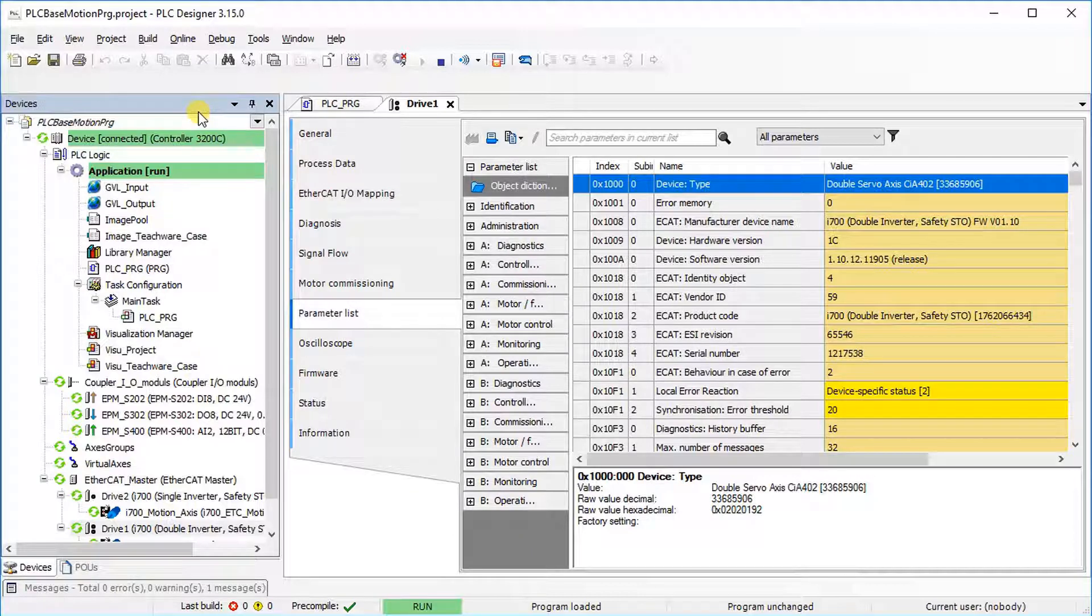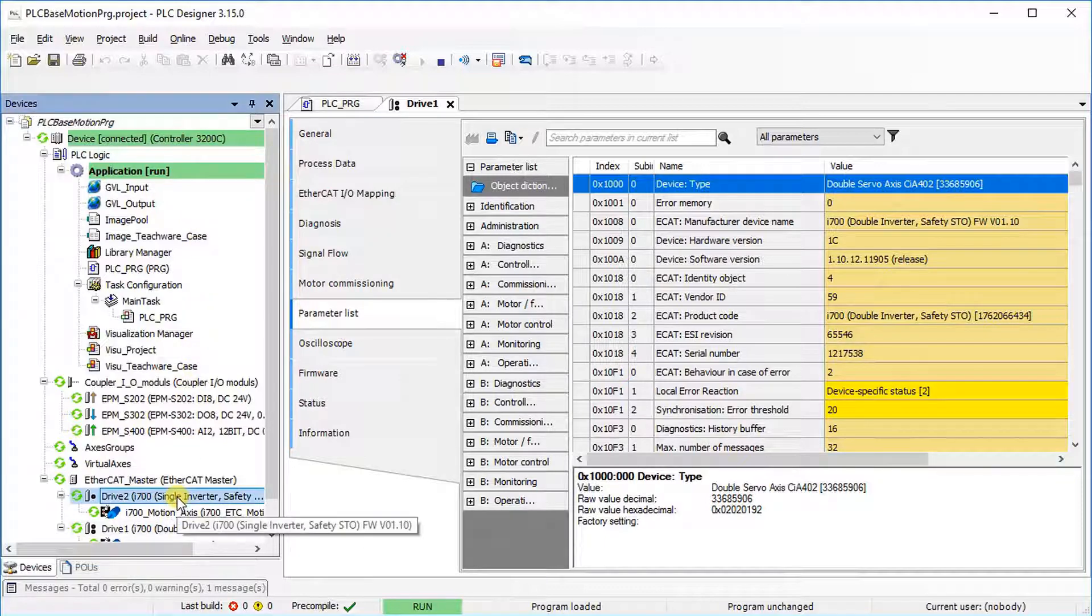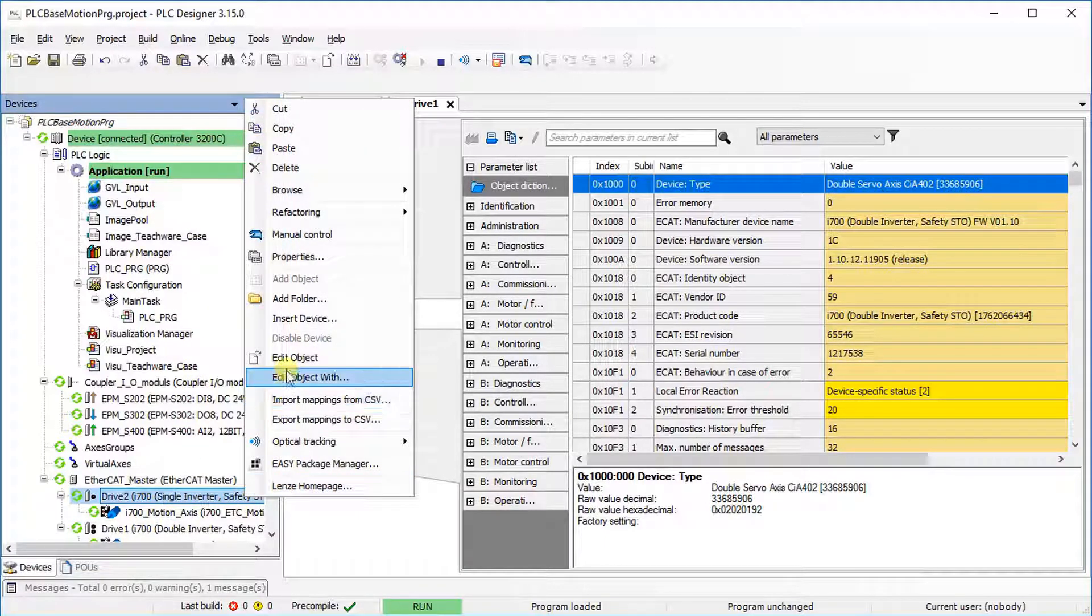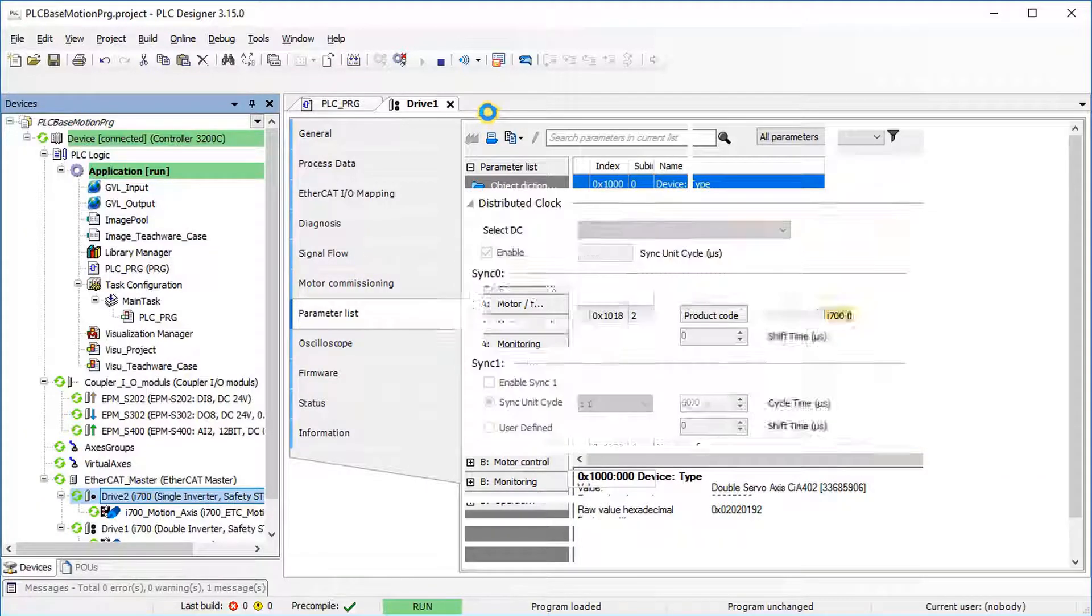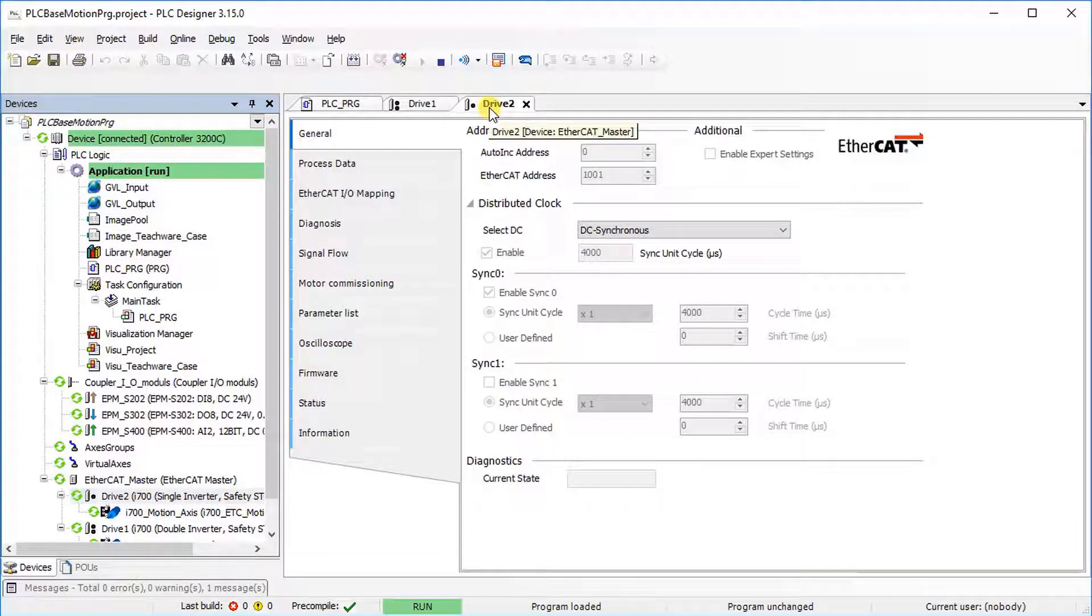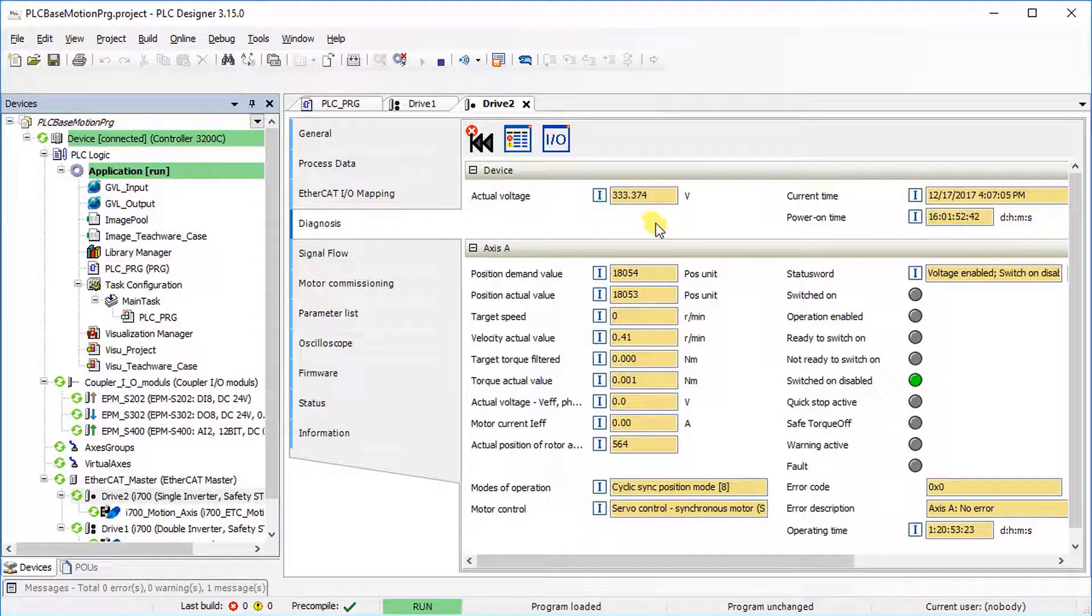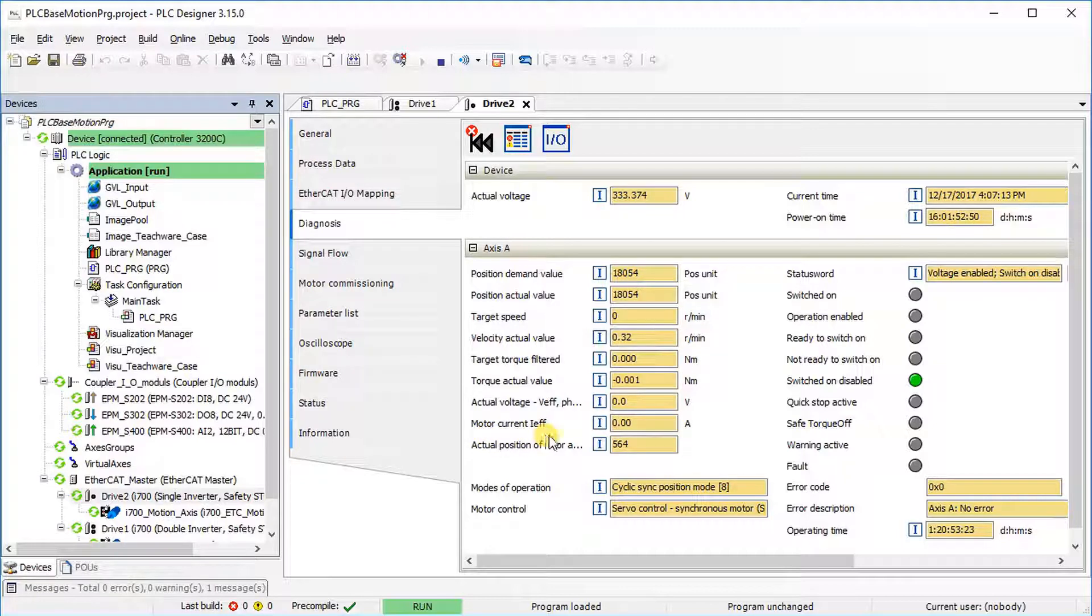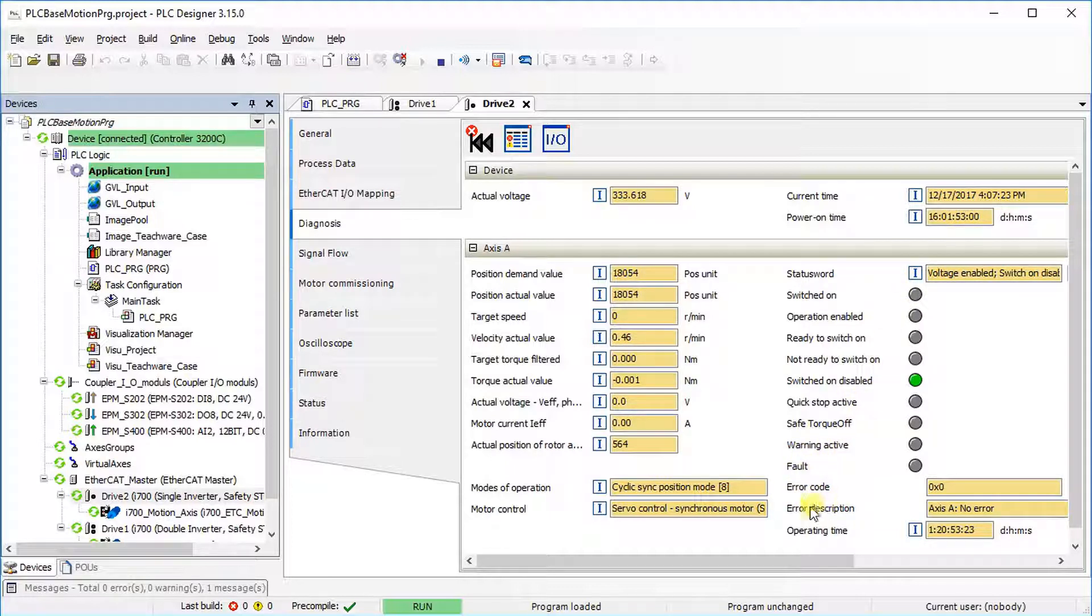Diagnosis of the drive is possible in online mode. Go to Device Settings of Drive 2 and choose Diagnosis. You can monitor the actual values of DC bus voltage, position, velocity, torque and current. You can also monitor the drive status word, fault and warning indications as well as error codes and error descriptions.